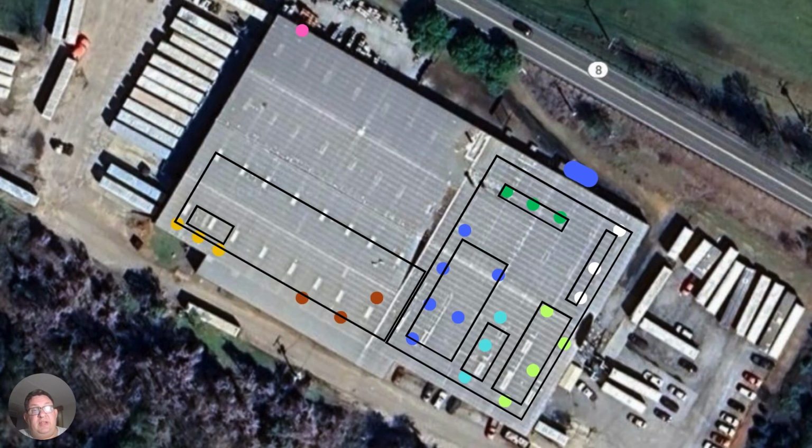Pick a subloop, pick the most critical or the biggest outlier to the facility, the zone that has the most differences from the rest of the plant, and now isolate that with its own subloop first. It's a small amount of piping. You can make sure it's properly sized. It's leak free. It has permanent monitoring on it. It has all the filtration and drying and instrumentation that it could want and need, as well as storage. And you can just move in pieces until you get the whole plant done.